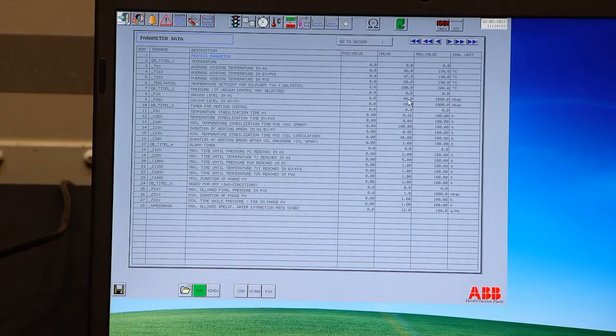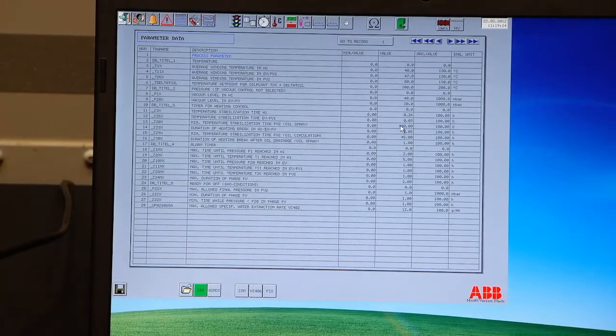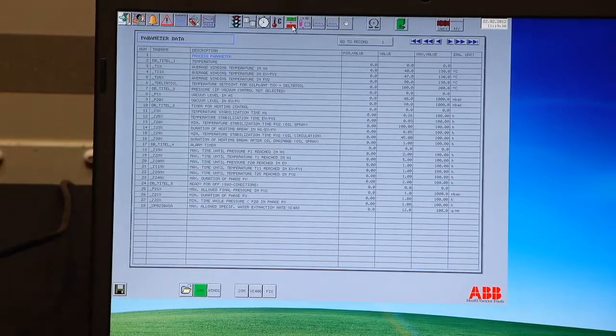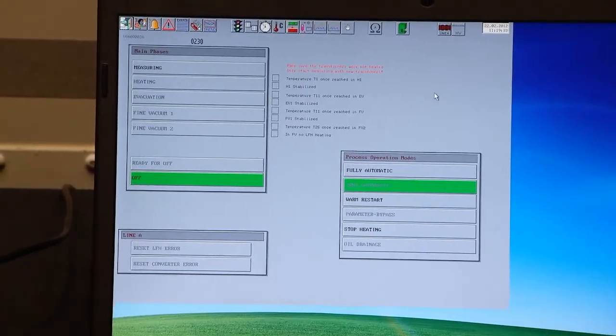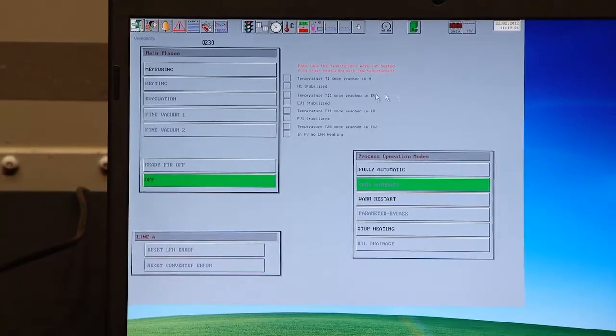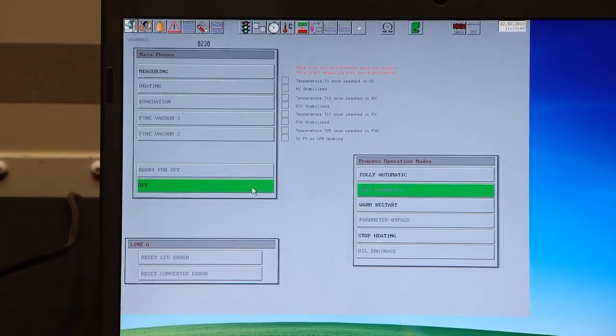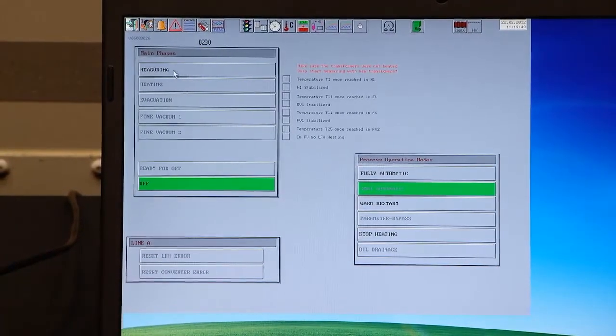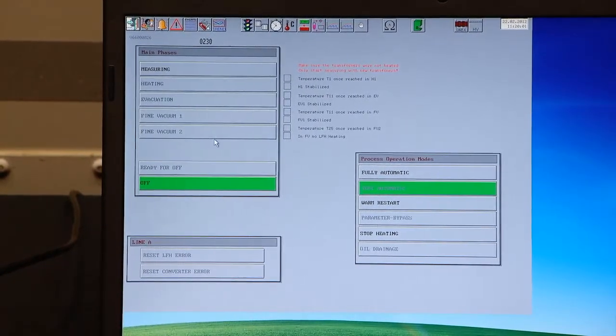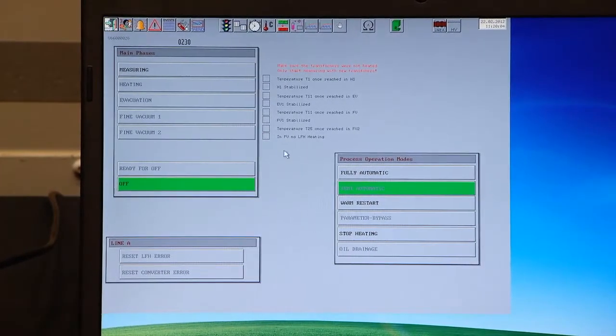Do we have the main disconnector closed? Then we're ready to go. We're coming to this page with the green and red stop and start page. This is where we have our phases. We are in off, that's highlighted green. Measuring is now with black text means we can select it. Heating is in gray, we cannot select it. We are in semi-automatic, which is the most normal one that we're going to use. Fully automatic means he's switching between each phase automatically. You will almost never use it.